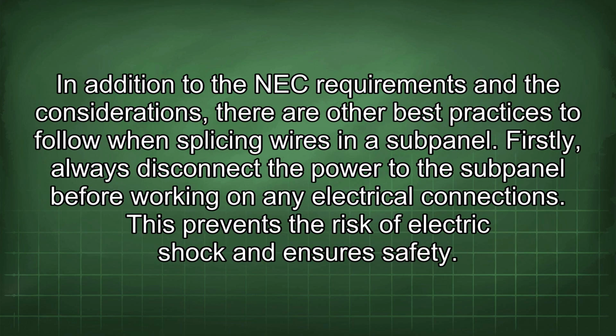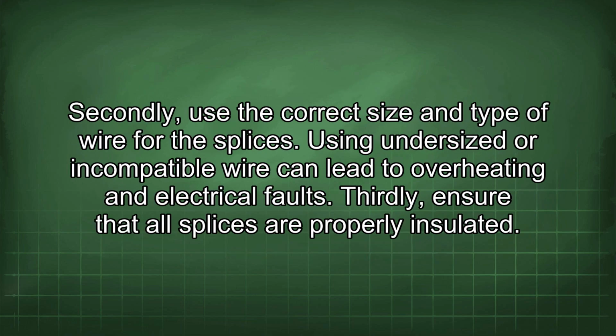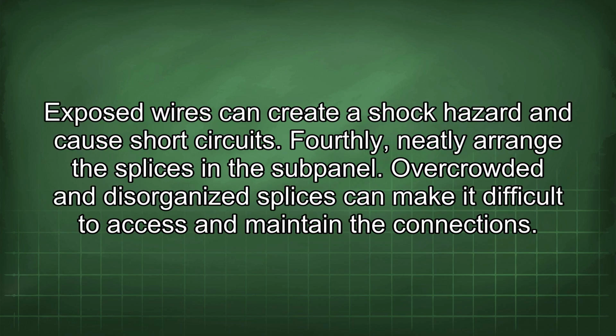In addition to the NEC requirements and the considerations, there are other best practices to follow when splicing wires in a subpanel. Firstly, always disconnect the power to the subpanel before working on any electrical connections. This prevents the risk of electric shock and ensures safety. Secondly, use the correct size and type of wire for the splices. Using undersized or incompatible wire can lead to overheating and electrical faults. Thirdly, ensure that all splices are properly insulated. Exposed wires can create a shock hazard and cause short circuits. Fourthly, neatly arrange the splices in the subpanel. Overcrowded and disorganized splices can make it difficult to access and maintain the connections.